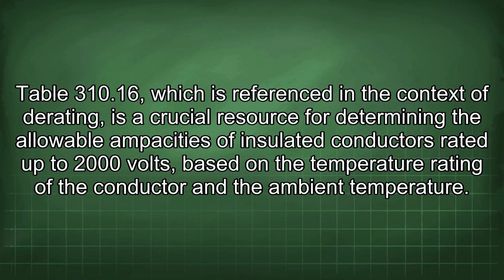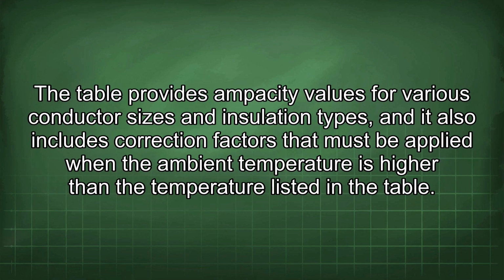Table 310.16, which is referenced in the context of derating, is a crucial resource for determining the allowable ampacities of insulated conductors rated up to 2000 volts based on the temperature rating of the conductor and the ambient temperature. The table provides ampacity values for various conductor sizes and insulation types, and it also includes correction factors that must be applied when the ambient temperature is higher than the temperature listed in the table.